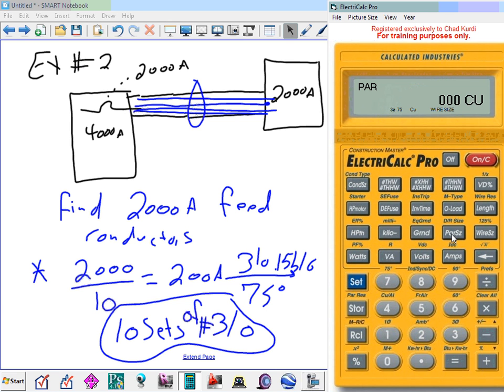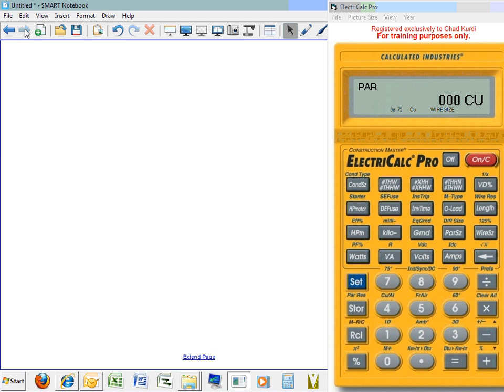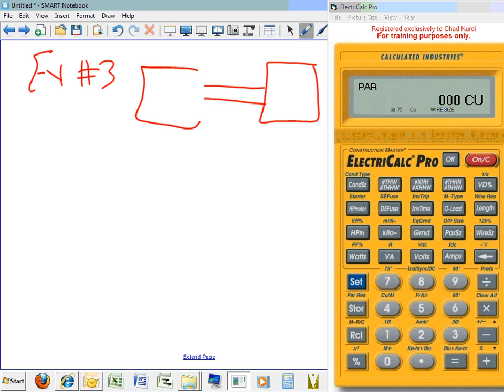But I decided to spice it up so I can derate. I need to derate based on temperature, and I want to make things more interesting. I need to derate based on temperature and also based on bundling. I just want to remind you guys, my calculation is 3-aught. Let's start with the 3-aught. Let's go back here and say example 2, example 3. Let's assume that whole scenario that I did before, 2000 amp and 4000 amp panel, and we size the conductors. We have 10 sets of 4 conductors, each one of them 3-aught.